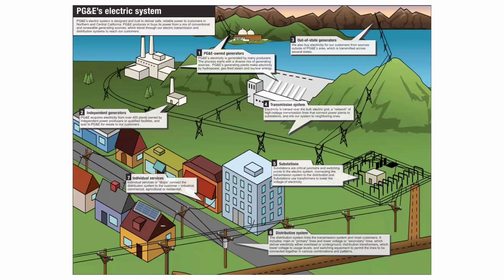So what EPIC 4.05 is doing is challenging those static assumptions that we've made in the past. PG&E, like many other utilities, operates on what's called a seasonal static limit, meaning we have ratings for the summertime and ratings for the wintertime. In both of these cases, there was a system-wide study to say here's what a reasonable assumption is for the weather, the wind, and the temperature.